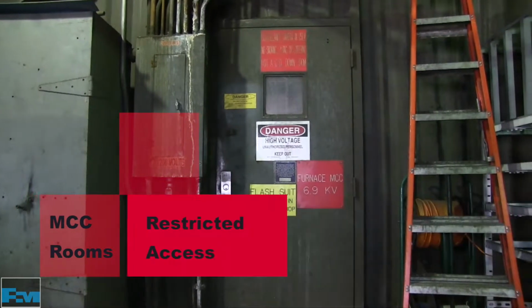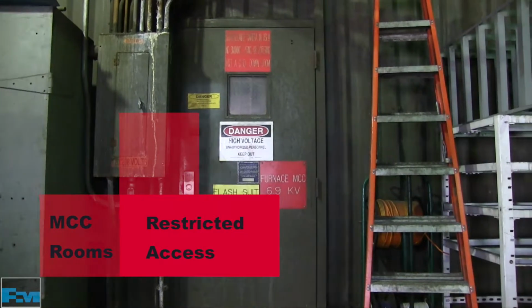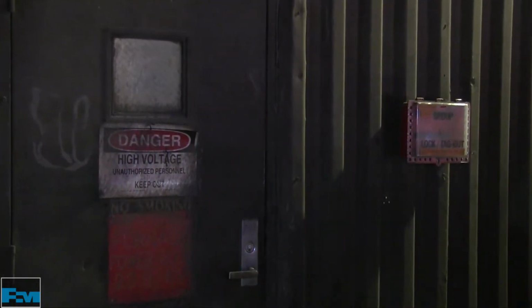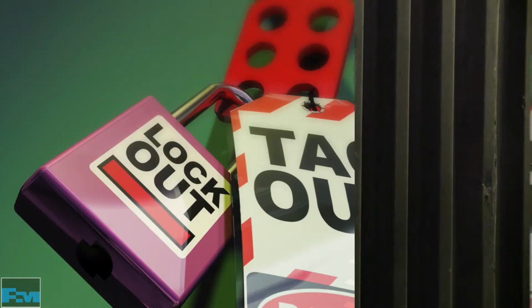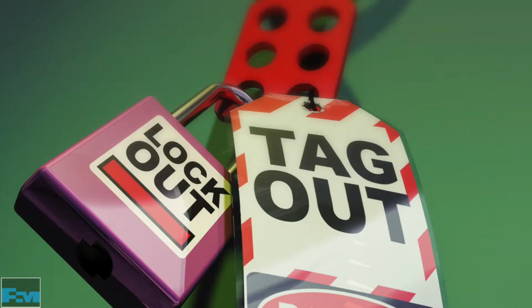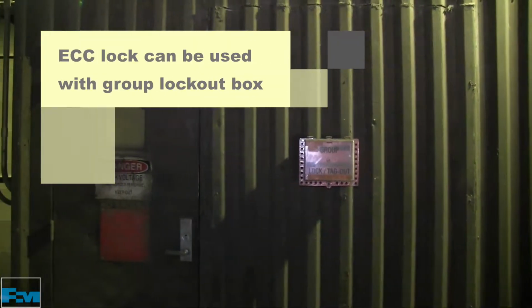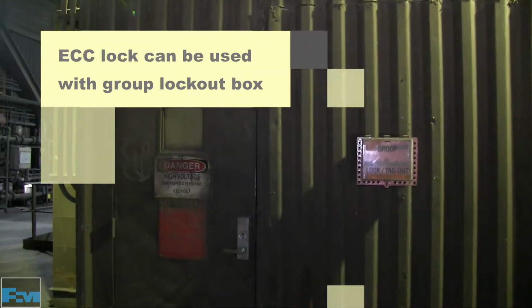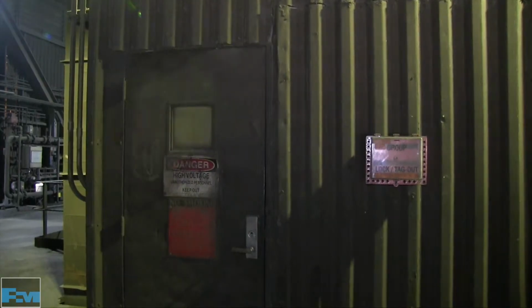Only electricians and authorized personnel are allowed inside the MCC rooms. When furnace power is locked out, only the electrician is allowed inside the room. The electrician will place the group lockout box outside the room where operations or maintenance personnel can put their personal lockout lock on it. An ECC lock can be used if there are several people using a group lockout box for the task.